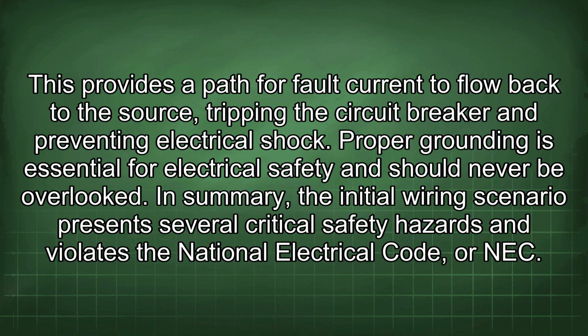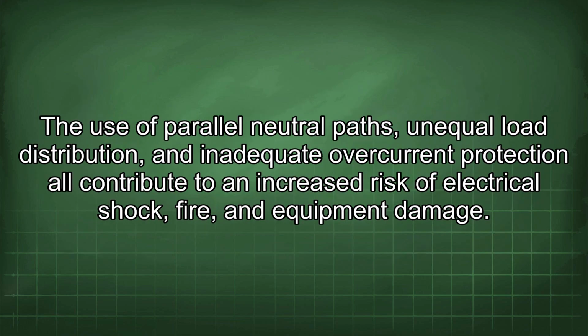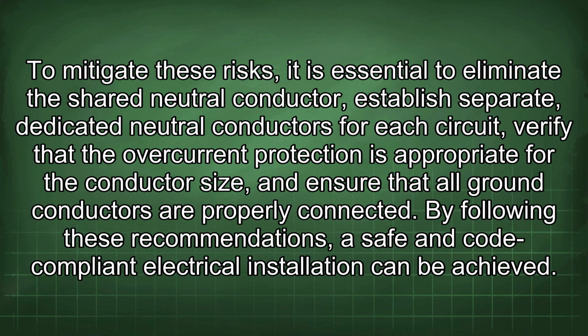In summary, the initial wiring scenario presents several critical safety hazards and violates the National Electrical Code, or NEC. The use of parallel neutral paths, unequal load distribution, and inadequate overcurrent protection all contribute to an increased risk of electrical shock, fire, and equipment damage. To mitigate these risks, it is essential to eliminate the shared neutral conductor, establish separate dedicated neutral conductors for each circuit, verify that the overcurrent protection is appropriate for the conductor size, and ensure that all ground conductors are properly connected. By following these recommendations, a safe and code-compliant electrical installation can be achieved.